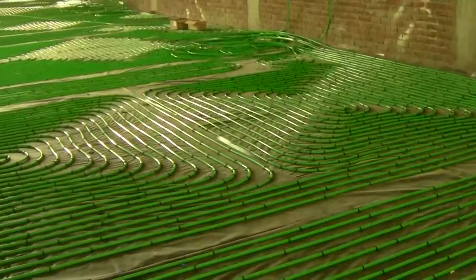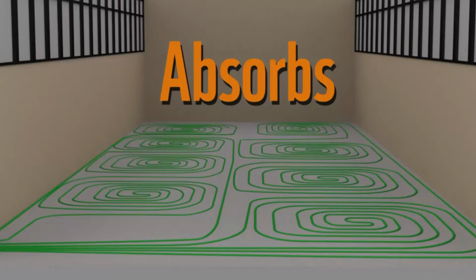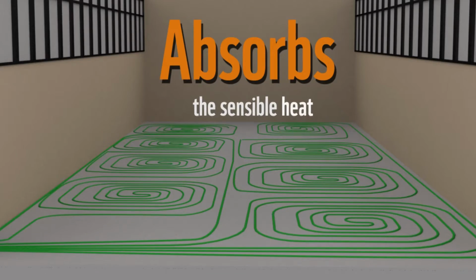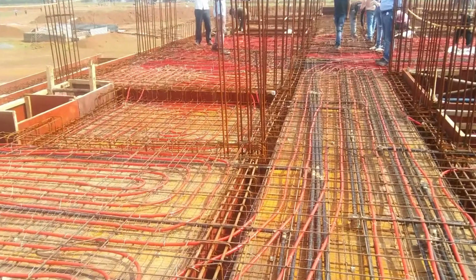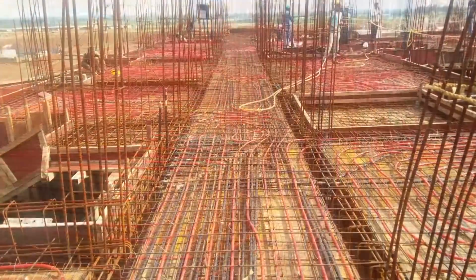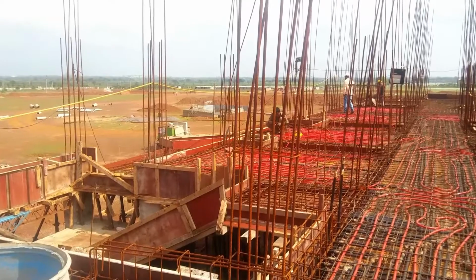This solution involves turning surfaces in the room, like the floor or ceiling, into a heat sink that absorbs the sensible heat in the room by embedding pipes in them, instead of blowing the air over a heat exchanger as is done in a conventional air handling unit.